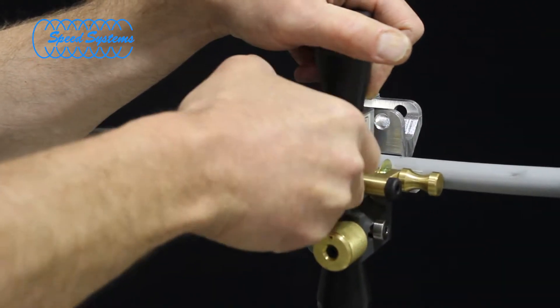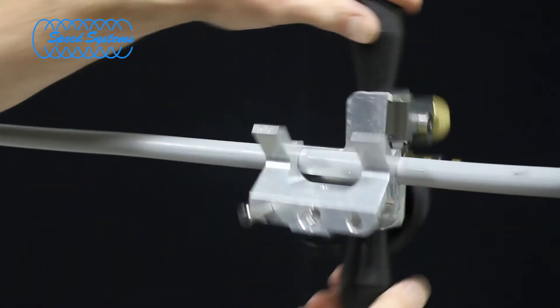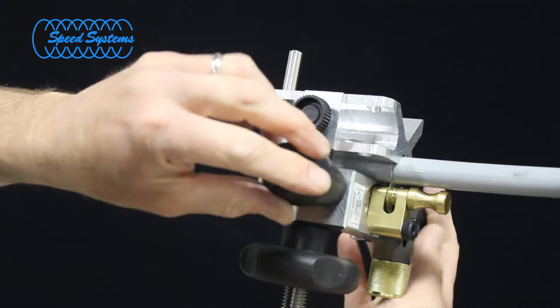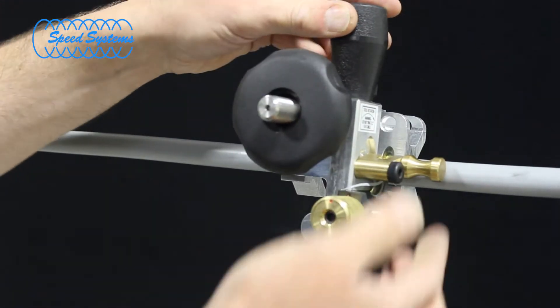Position the tool on the cable and tighten the cable clamp knob until the ringing blade is fully engaged. Rotate the tool one revolution in the direction shown on the tool block. Rotate the tool backwards approximately one eighth of a turn and move the ringing blade to the fully up position.